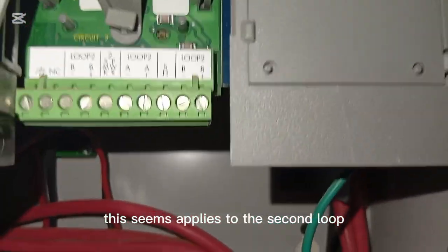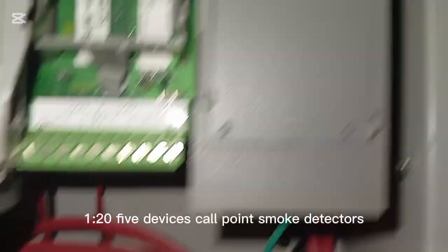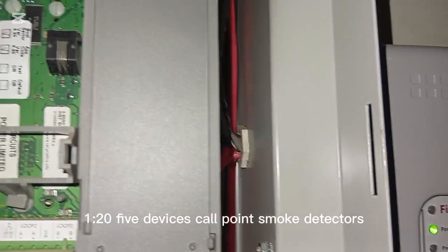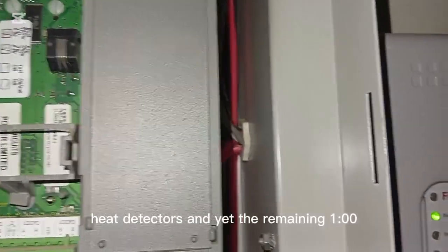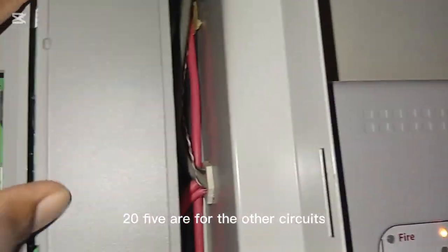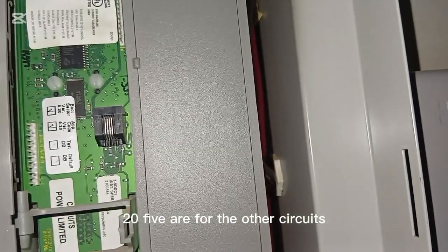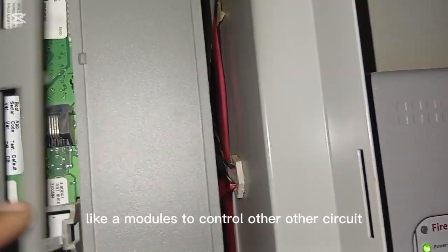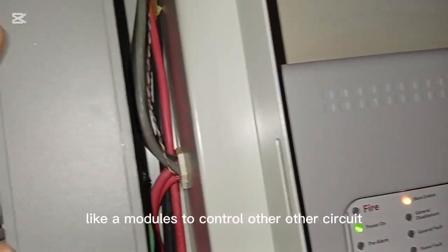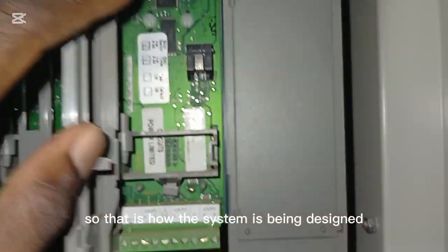The other 125 devices carry all the modules you will add in the system. The same applies to the second loop: 125 devices, call points, smoke detectors, heat detectors, and the remaining 125 are for other circuits, like modules to control other circuits. So that is how the system is designed.